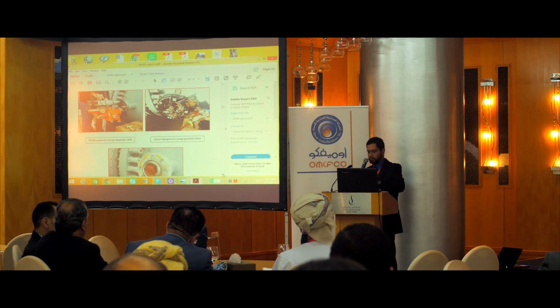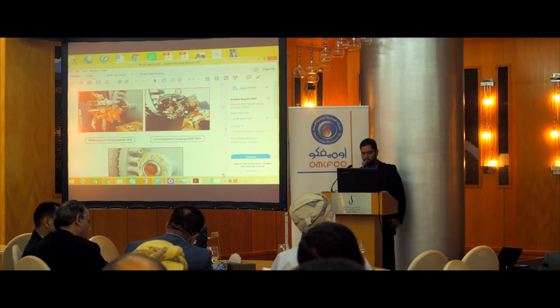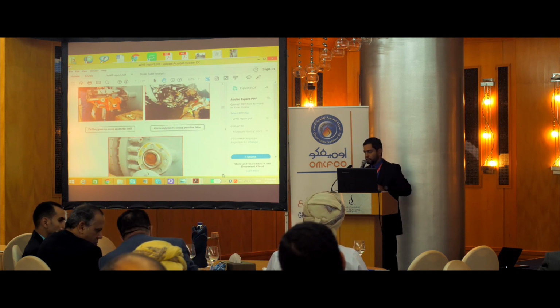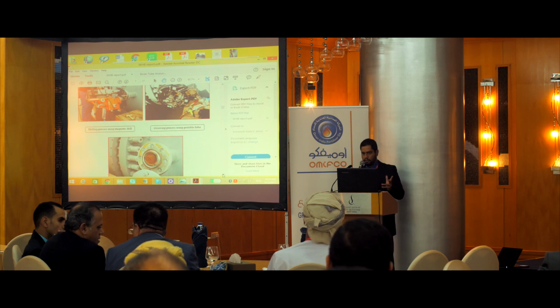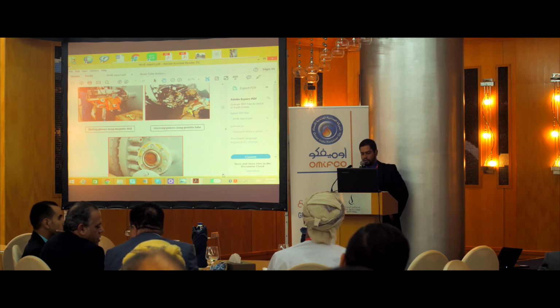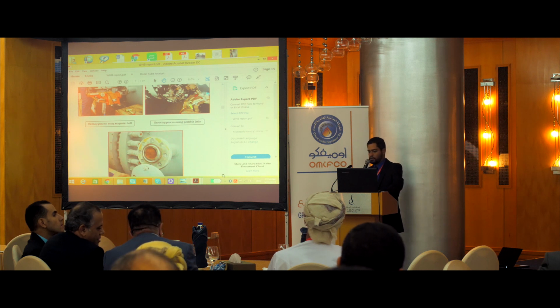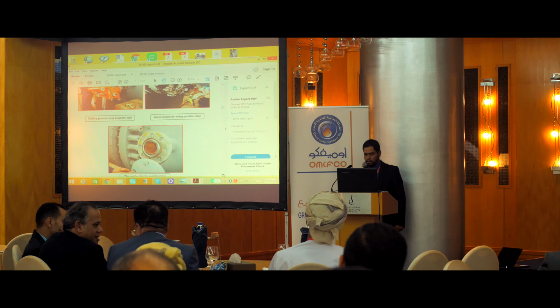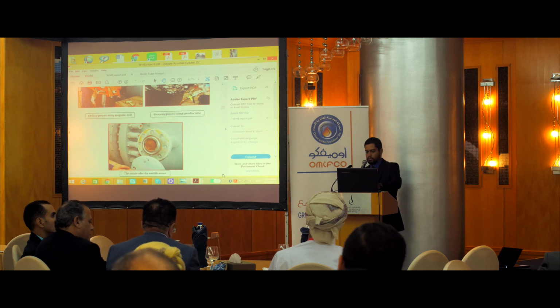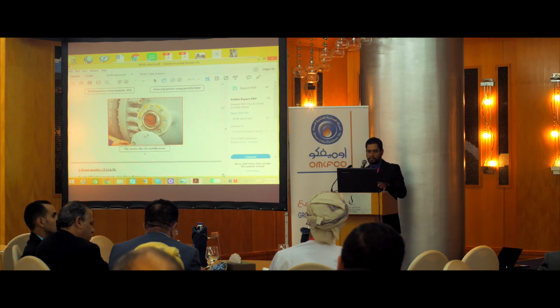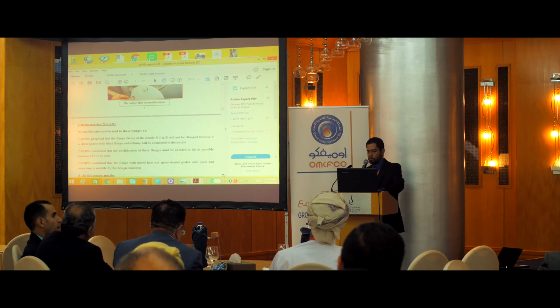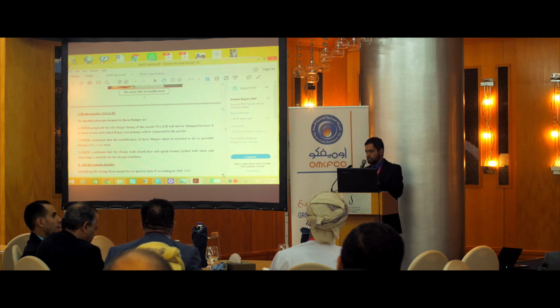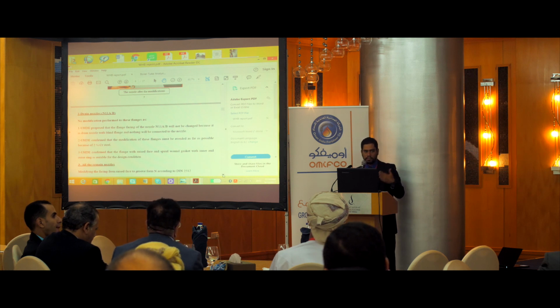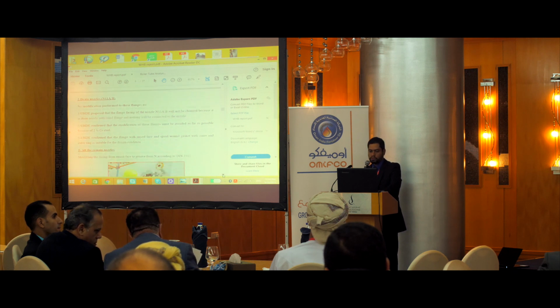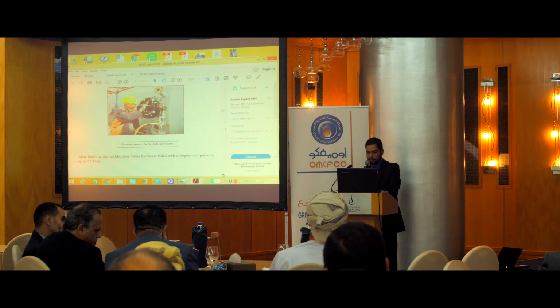And there were some problems in the flanges of the waste heat boiler on the steam or the water side. The water side flanges are tongue and groove, but the supplier delivered raised face flanges. So we used a portable lathe and modified the flanges. All of these activities were done before the shutdown, so we started before the shutdown to reduce the time and increase the productivity of the plant.